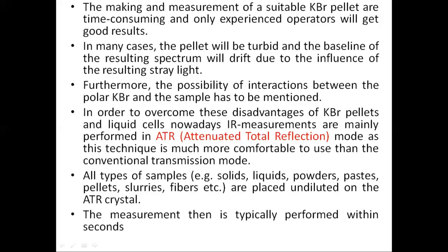In order to overcome these disadvantages of KBr pellets and liquid cells, nowadays IR measurements are mainly performed in ATR, that is attenuated total reflection mode, as this technique is much more comfortable to use than the conventional transmission mode. All types of samples, for example solids, liquids, powders, pastes, pellets, slurries, and fibers, are placed undiluted on the ATR crystal. The measurement then is typically performed within seconds.